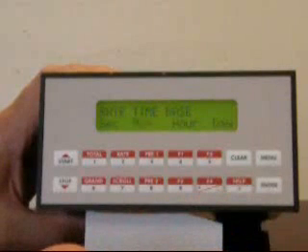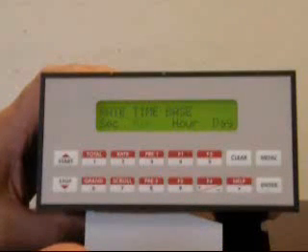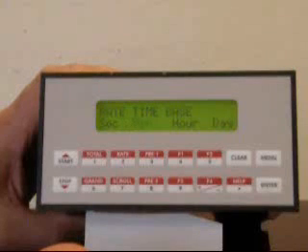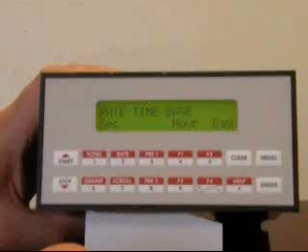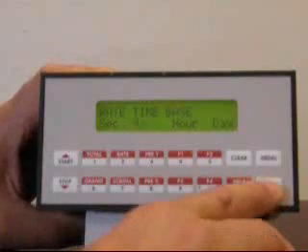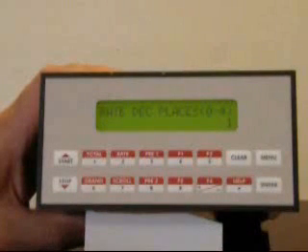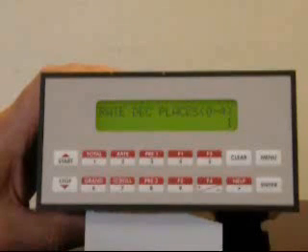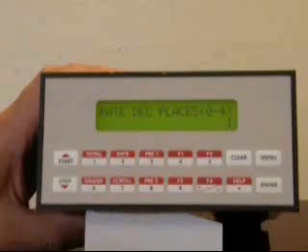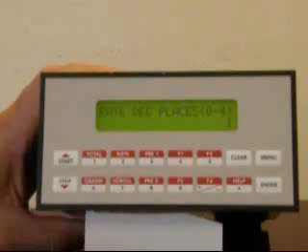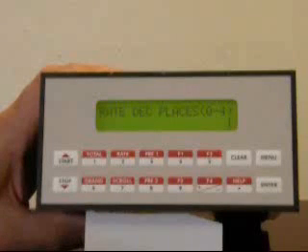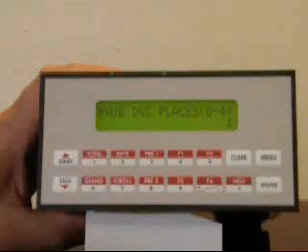It will now offer you a selection on whether you wish to observe the rate in units per minute, per hour, per day, or per second. Let's use minutes. It will now offer you a selection for the number of decimal places you wish to see on the rate display. Many users indicating in gallons per minute, for example, may wish to either read in whole gallons per minute or perhaps down to one tenth gallons per minute. A selection of one indicates that you wish to see one place beyond the decimal. And we're going to use that selection.